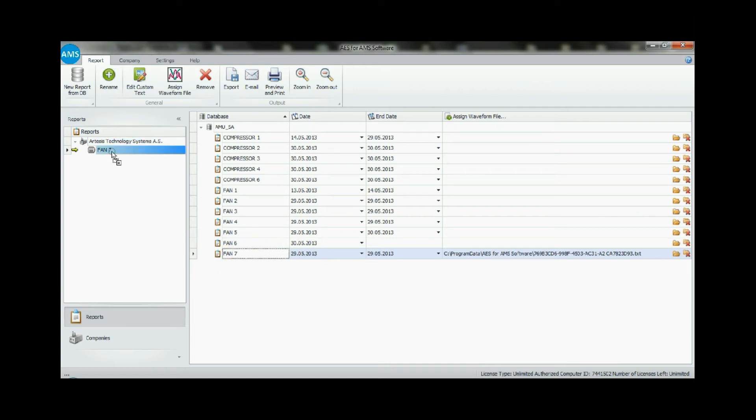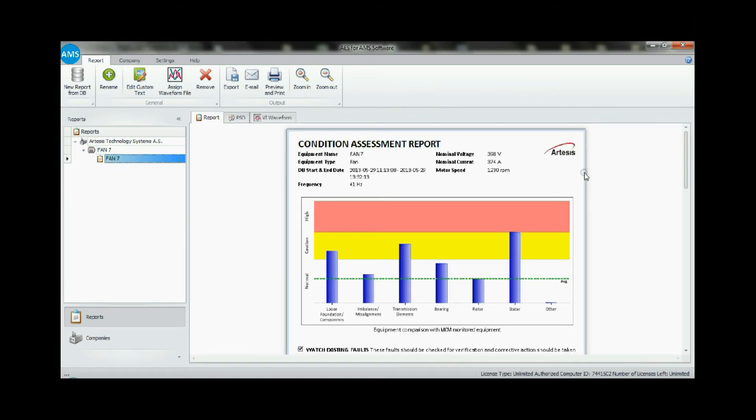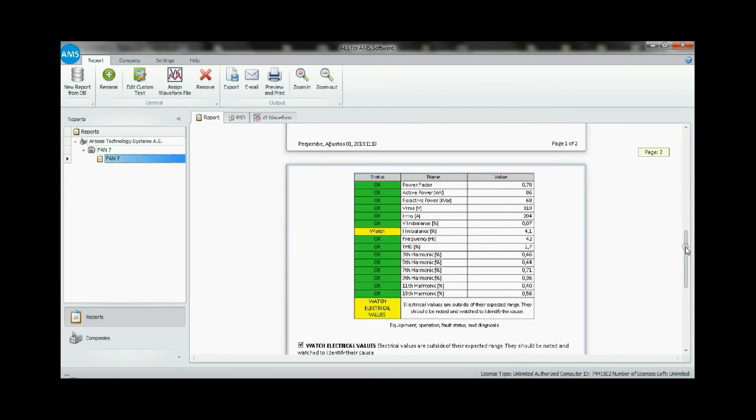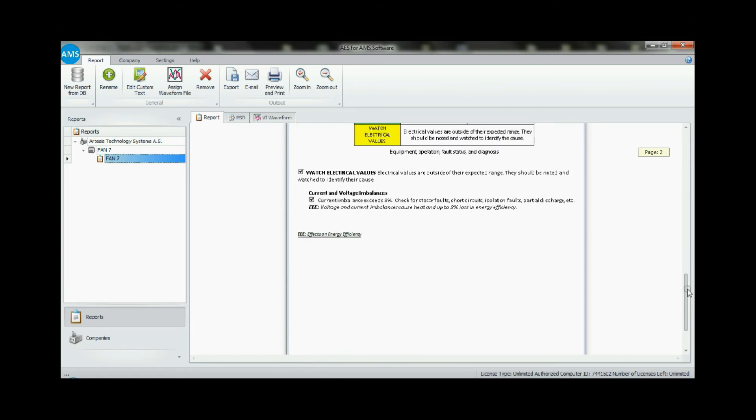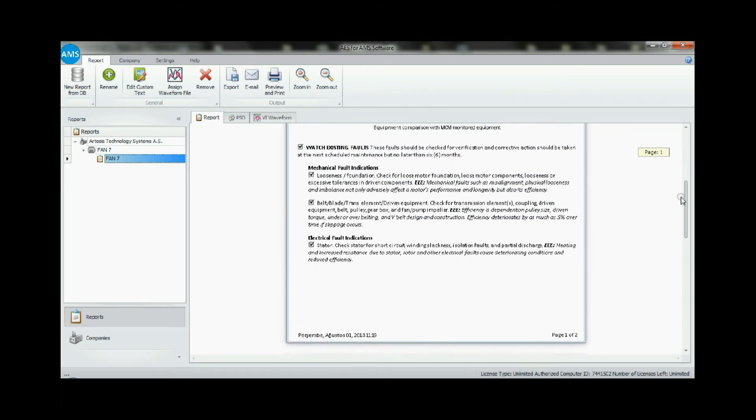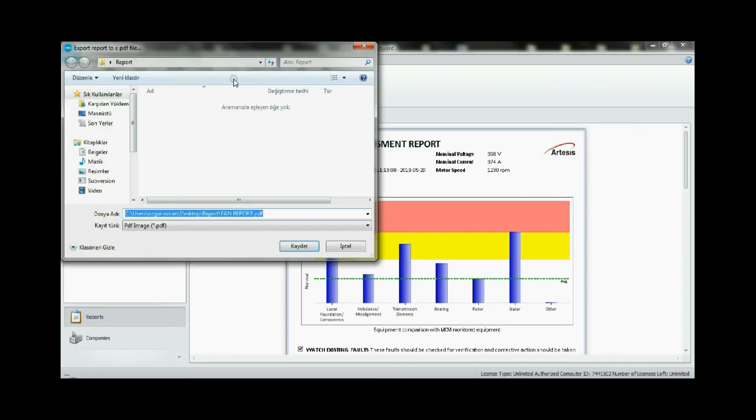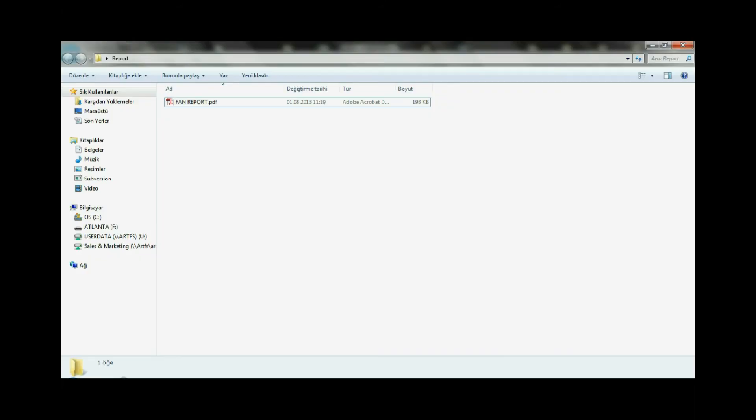This report identifies any existing mechanical or electrical problems, recommends corrective actions and how soon such actions should be carried out. The report also provides measured electrical parameters such as power factor, active and reactive power, voltages, currents and their imbalances, as well as harmonics. If these electrical parameters are above their expected values, a warning is issued for the attention of the user.